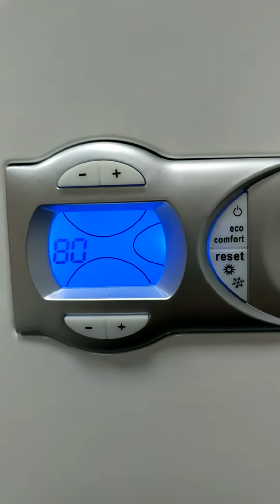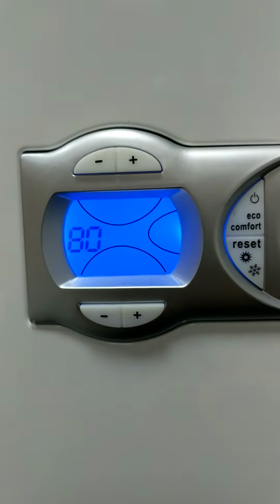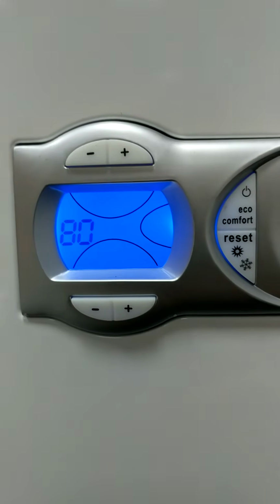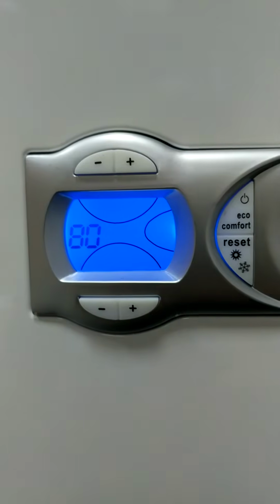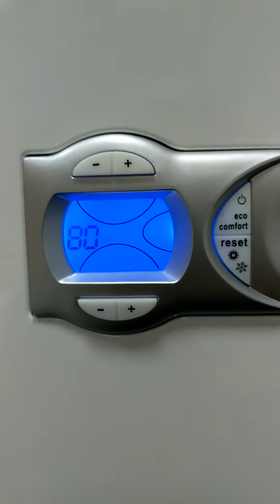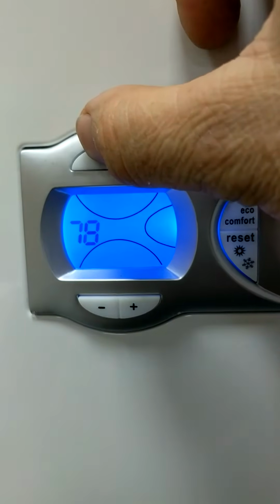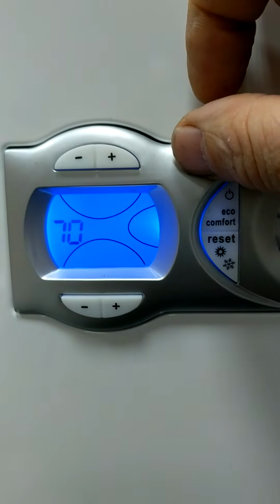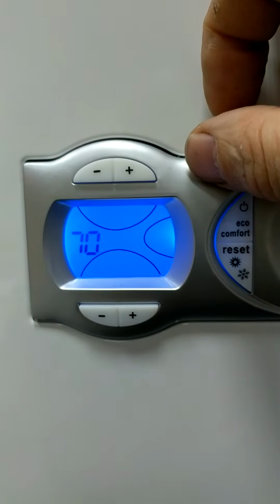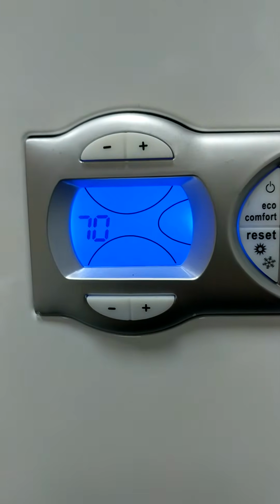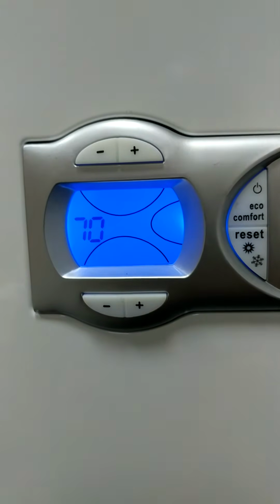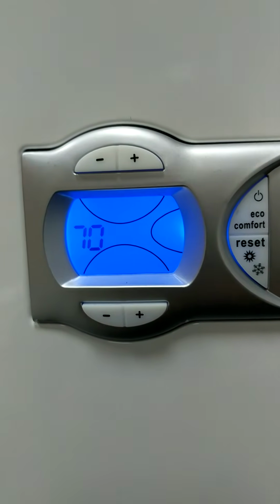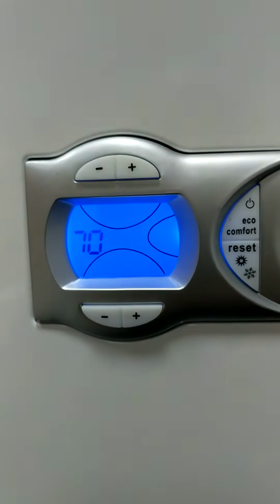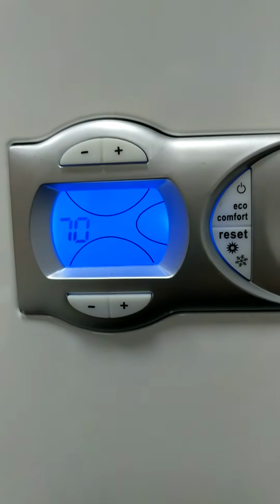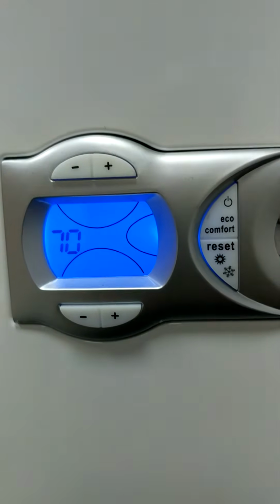So if you set it to about 100 degrees, the customer can actually put this boiler to 100 degrees, and if they've got all the radiators turned off, it might even overheat. So what we do, we sort of cap it off, let's say 70 to 80, and this is the actual temperature limit set point. Just a point on the actual temperature, when you do set it, when you come out the parameters, this boiler doesn't actually physically acknowledge the temperature you want until 10 degrees after.